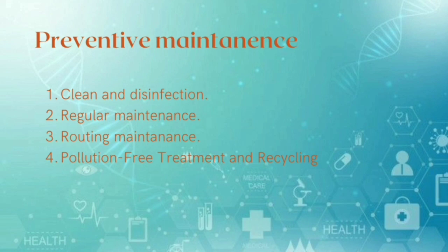Third one is routine maintenance. Thoroughly clean the syringe shell before or after a long period of storage. Check the AC power plug and cord. Run the syringe pump with battery until the alarm of low power rings, and then charge the battery. Please make sure the operation and charge is normal.